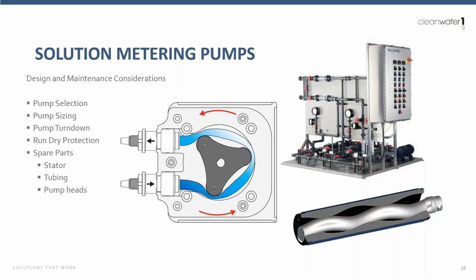But we want to make sure the pump sizing is correct. We want to make sure the pump turn down is correct. And then for those peristaltic pumps, we want to make sure that they have run dry protection, we want to make sure they have tube leak detection. And then we want to have run dry protection for progressive cavity pumps. This is an item where it's really important to have spare parts on hand, right? A spare stator for a progressive cavity pump, a spare tubing or tube head for a diaphragm pump or a peristaltic pump. So design considerations really come in hand here as far as sizing, turn down, and maintenance.